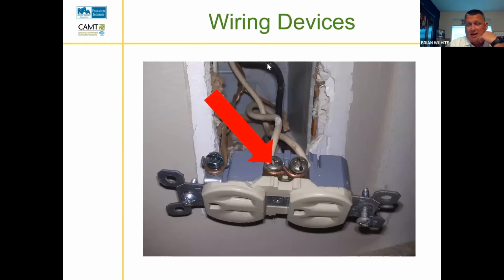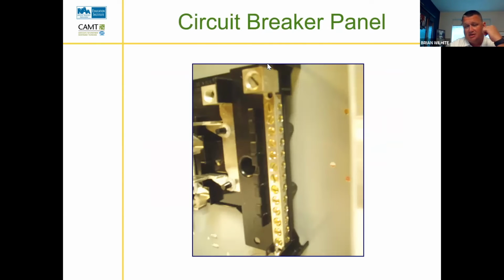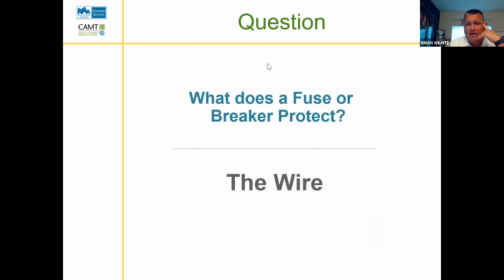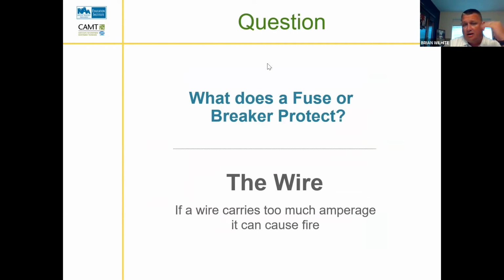So at the end of the day, especially for your test, and I should bang on some because it'll be on your test, what does a fuse or a breaker protect? It protects the wire. If the wire carries too much amperage, it will cause a fire. So it does protect the other things, but bottom line, it protects the wire, because without the wire, none of the other things work. None of the other things are possible.